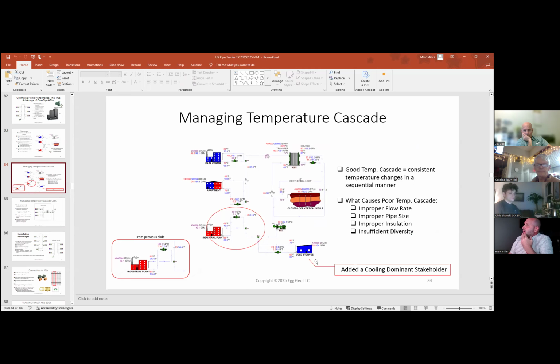So now, managing temperature cascade, all right, same diagram, all right? What I've done in this one, though, is I've added a cooling dominant stakeholder onto the loop after the fact, okay? Cold storage. So this could be a grocery store. Grocery stores are cooling dominant, all right? Now, if we look at the loop, what did that do to our loop? So we still have the same discharge temperatures, right? 85 and 65. We're still maintaining the 75 degree on the loop. We still got the 75 coming back in, but let's look at what the differences are.